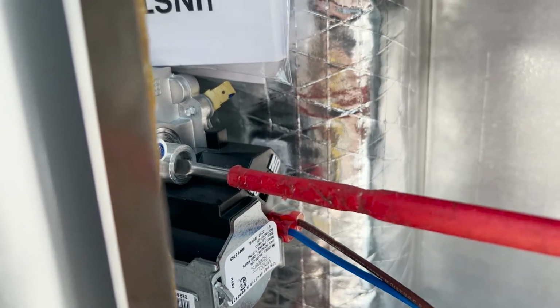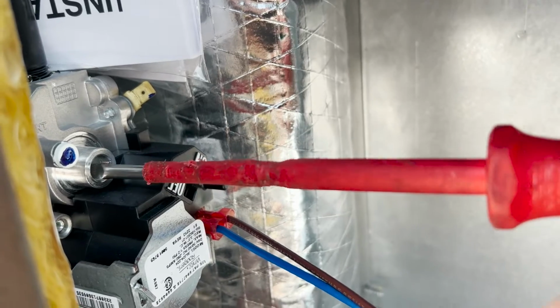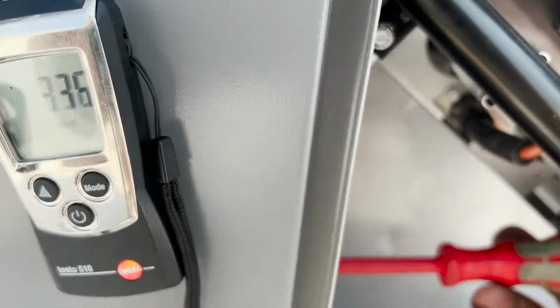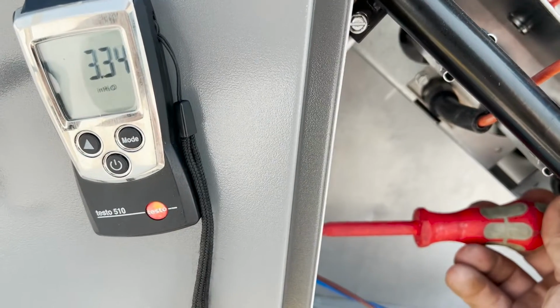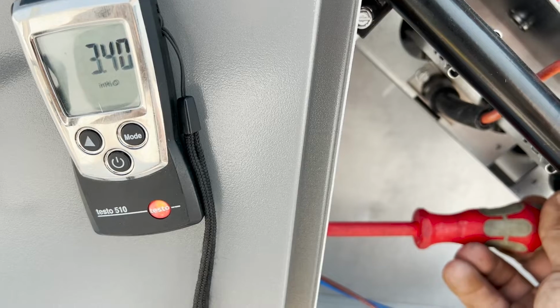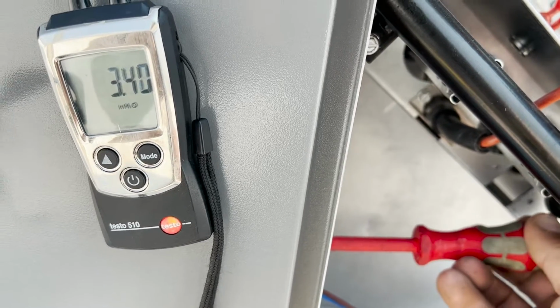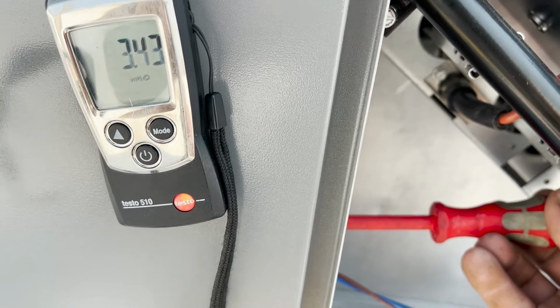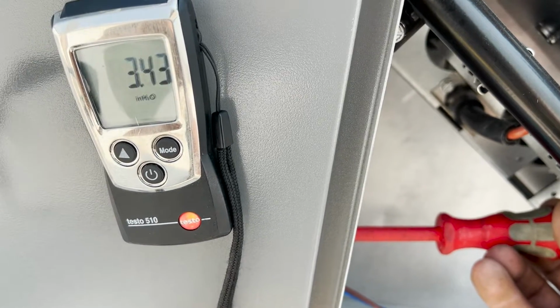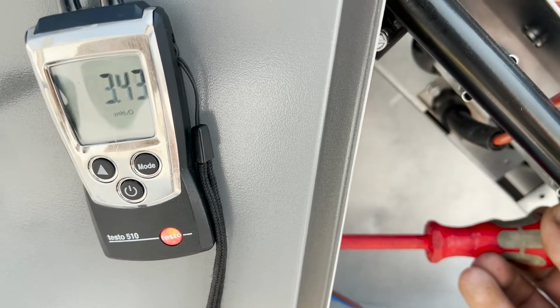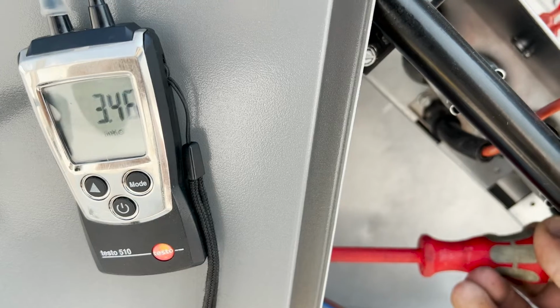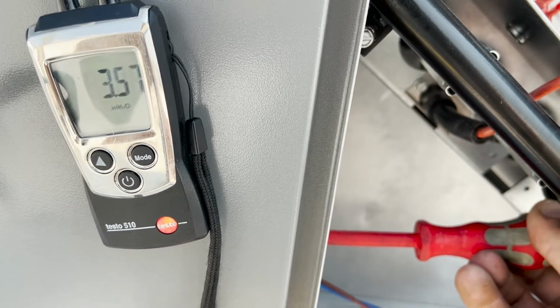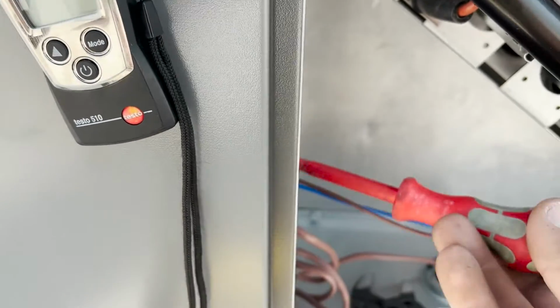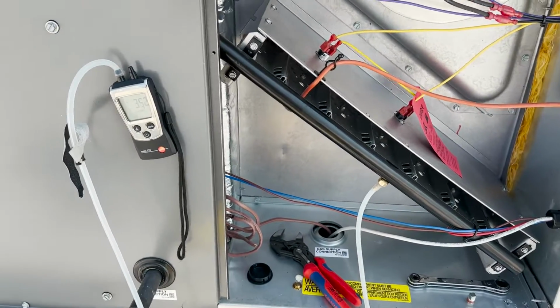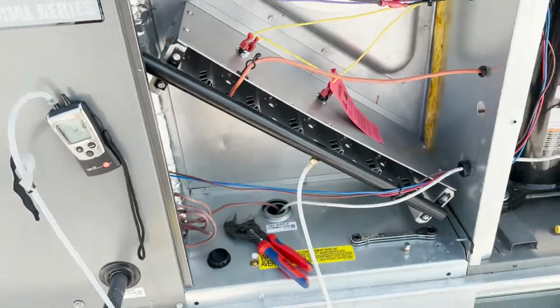All right, we already took off our adjustment cap. We're gonna get our screwdriver seated. Okay. And then small turns. This is not a force it situation. Make good contact, make good clean turn. That'll do it. We want our average to be about 3.5. We'll let that run for a second, but then we'll get our cap back on and we're good to go.